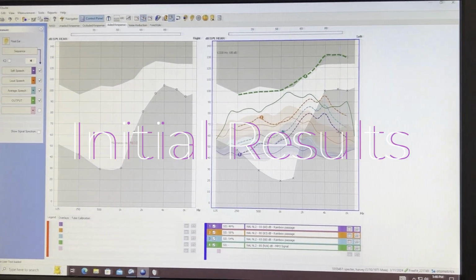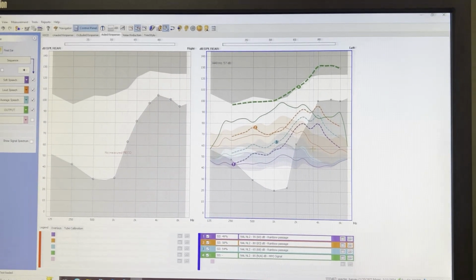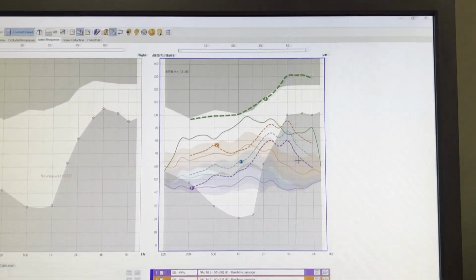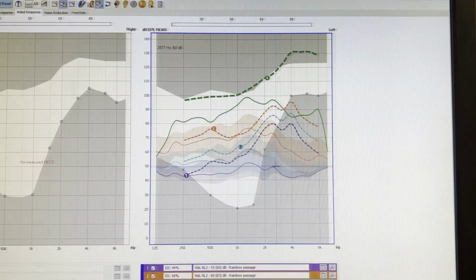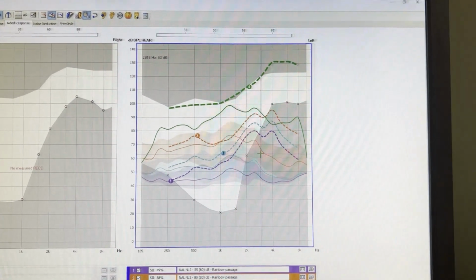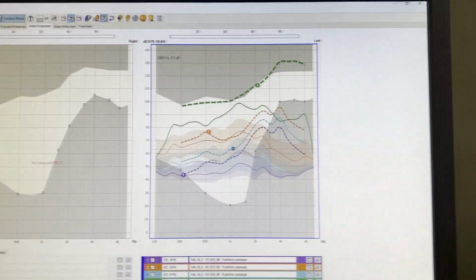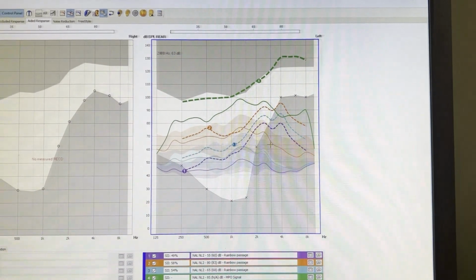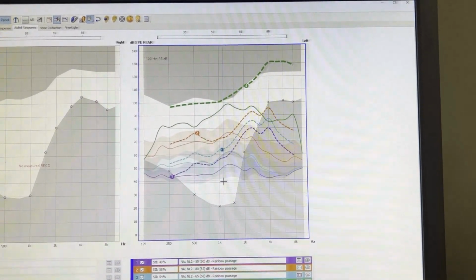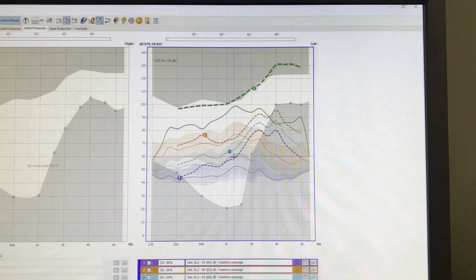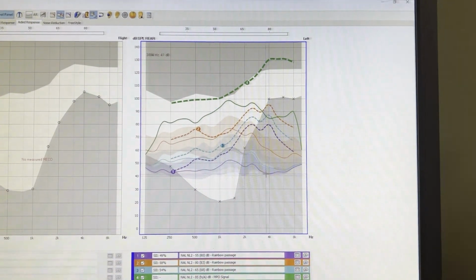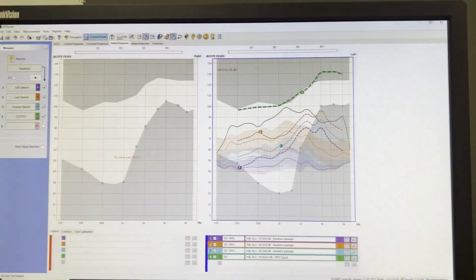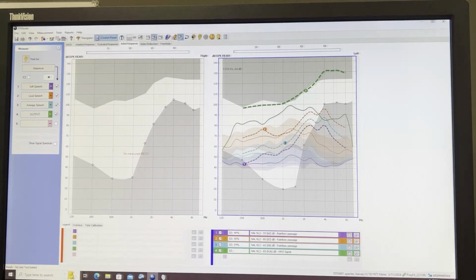All right, so as you can see here, we have our results of the speech mapping. Obviously, they're not great because we don't have a hearing aid hooked up to it. But what we would do is we would go into the hearing aid software and we would adjust our fine tunings, and then we would run speech mapping again. So that way we can get our measurements closer to our targets. The targets are the dotted lines, the measurements are our measurements. And that is how you do speech mapping on ear for the Auricle.